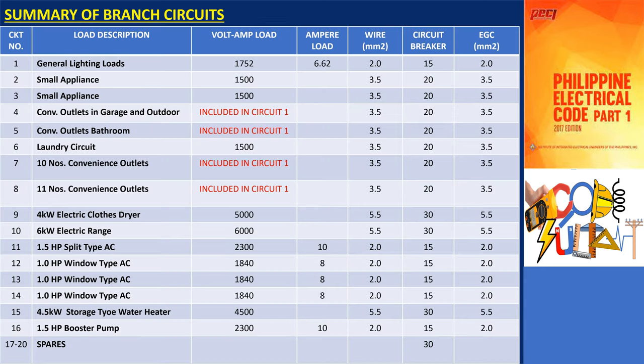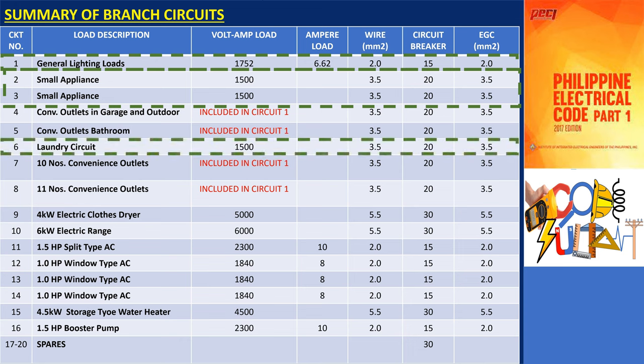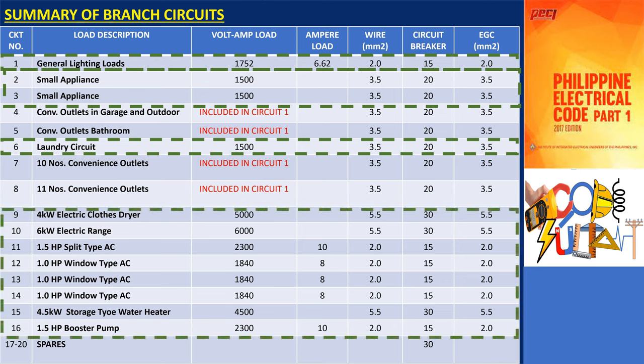1. The number of small appliance circuits — this project requires two circuits for small appliances. 2. General lighting load and receptacle outlets — the total load amounts to 1,752 volt amperes. 3. Laundry circuits — contributing 1,500 volt amperes. 4. All individual appliance branch circuits — these must be included in the calculation of feeders and service equipment. Furthermore, it is important to account for future expansion, allowing for a 20% increase, by providing spare circuit breakers and conduits.